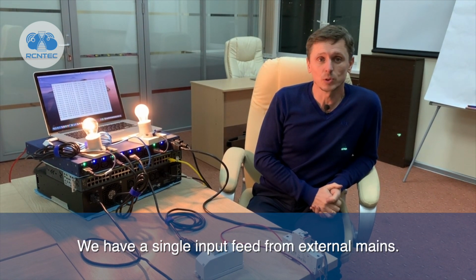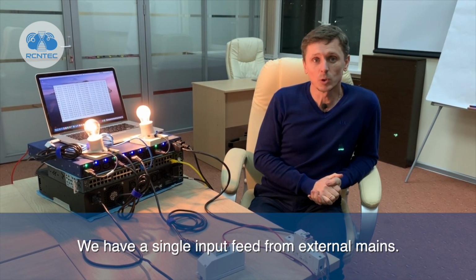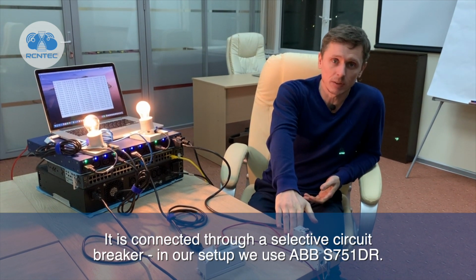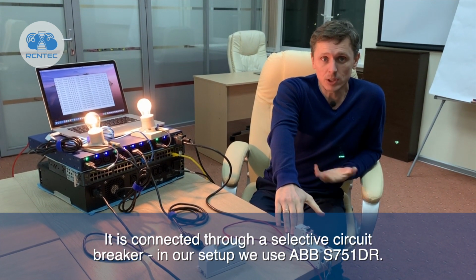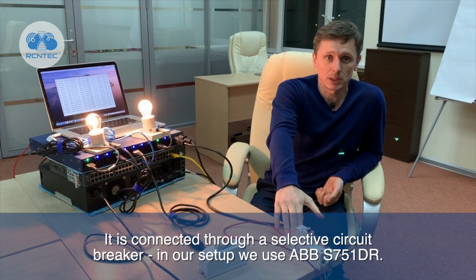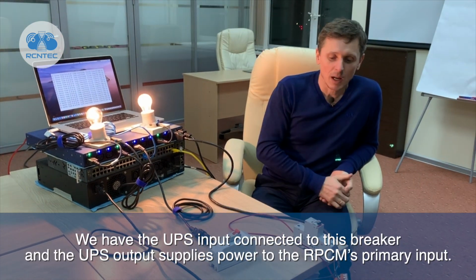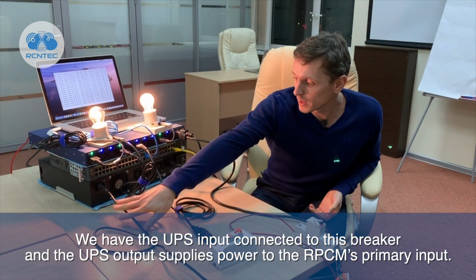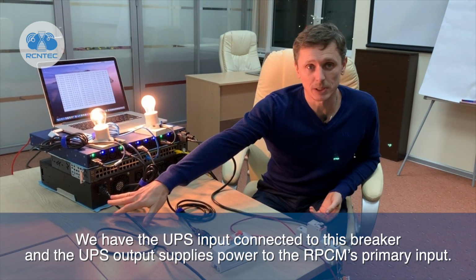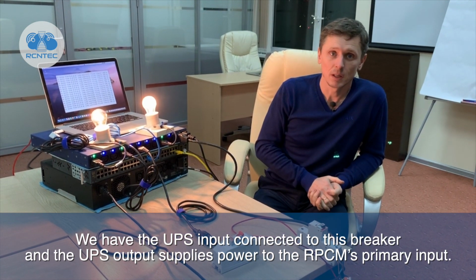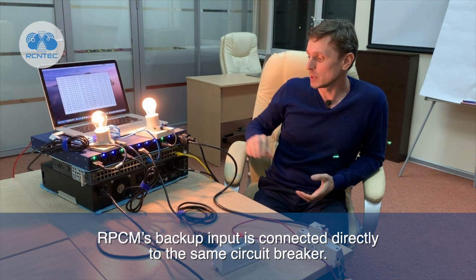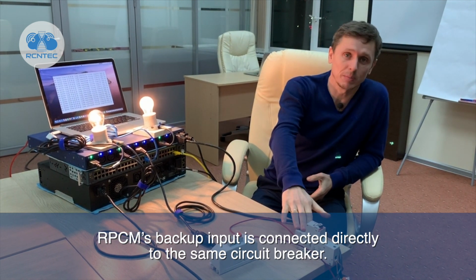We have a single input feed from external mains. It is connected through a selective circuit breaker. In our setup we use ABB S751DR. We have the UPS input connected to this breaker, and the UPS output supplies power to the RPCM's primary input. RPCM's backup input is connected directly to the same circuit breaker.